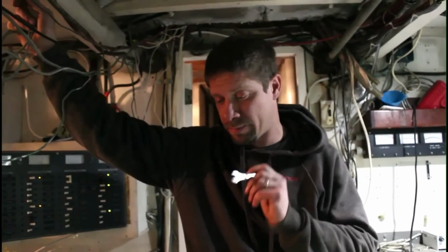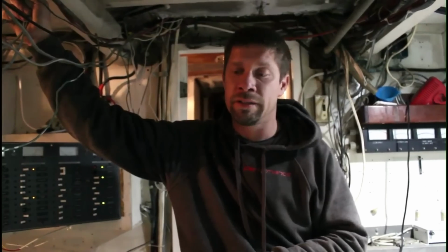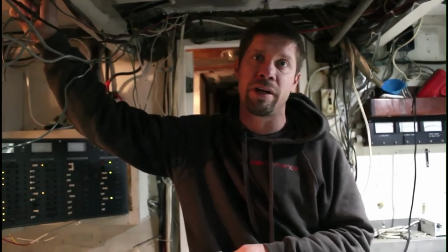So basically the rod bearing fails, and you've got to tear down the generator and rebuild it. Not only that, being an AC generator head, our inverters were only able to charge at about 75 amps, so that gives us a total charging of 140 amps. It just wasn't going to do it - the charge times would have been too high, the generator would have been super unloaded, which isn't good for them either. They'll glaze up. So we needed something better.